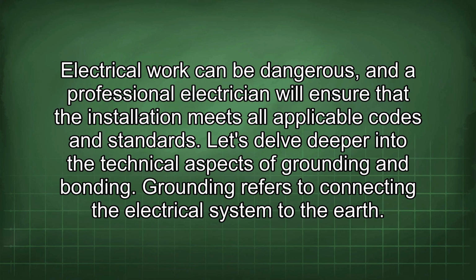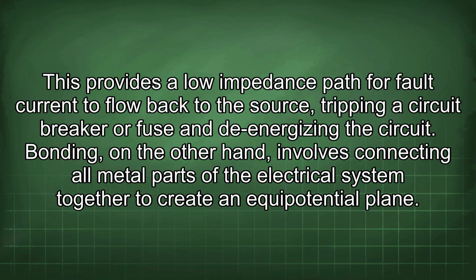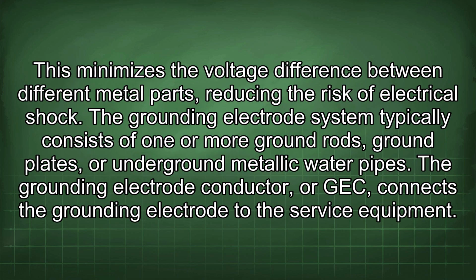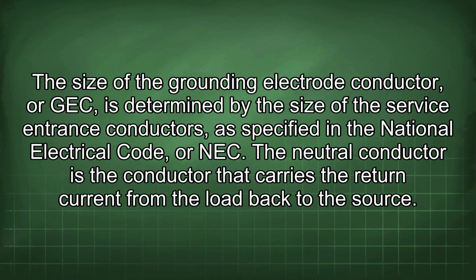Grounding refers to connecting the electrical system to the earth. This provides a low impedance path for fault current to flow back to the source, tripping a circuit breaker or a fuse and de-energizing the circuit. Bonding, on the other hand, involves connecting all metal parts of the electrical system together to create an equipotential plane. This minimizes the voltage difference between different metal parts, reducing the risk of electrical shock. The grounding electrode system typically consists of one or more ground rods, ground plates, or underground metallic water pipes. The grounding electrode conductor, or GEC, connects the grounding electrode to the service equipment. The size of the GEC is determined by the size of the service entrance conductors as specified in the National Electrical Code, or NEC.